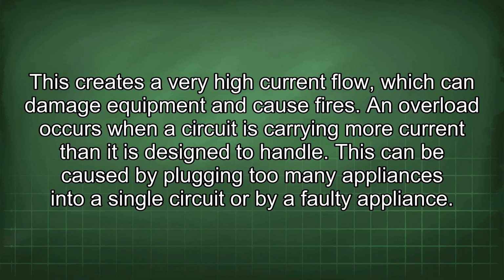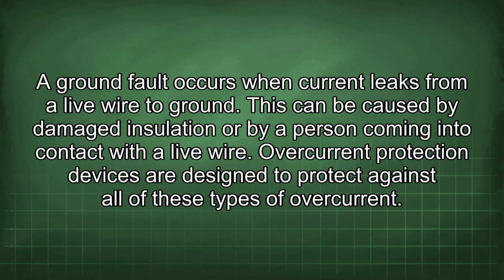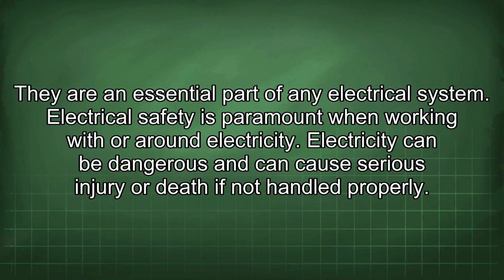An overload occurs when a circuit is carrying more current than it is designed to handle. This can be caused by plugging too many appliances into a single circuit or by a faulty appliance. A ground fault occurs when current leaks from a live wire to ground. This can be caused by damaged insulation or by a person coming into contact with a live wire. Overcurrent protection devices are designed to protect against all of these types of overcurrent. They are an essential part of any electrical system.